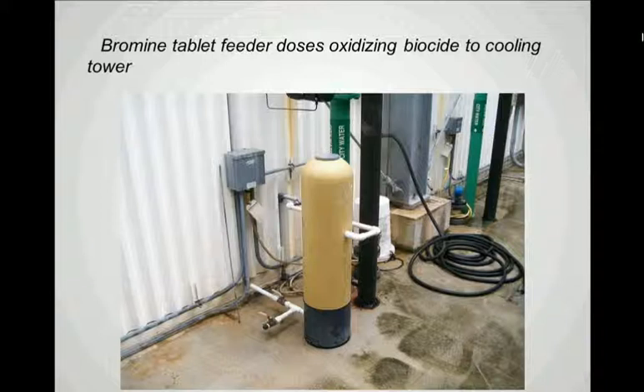algae. And if you don't provide adequate provisions for controlling these bacterial growths in the system, you'll soon find that you have a Garden of Eden of algae growing in the tower, and it also can have some health effects with certain microorganisms like Legionella, which can pose an environmental health threat if not properly controlled. So again, this system is commonly fed off the controller, and it's automated, so we maintain the dosages within the prescribed limits for that sanitizer. Alternatives include chlorine and other non-oxidizing biocides that can and are often used to control bacteria and microbiological fouling.